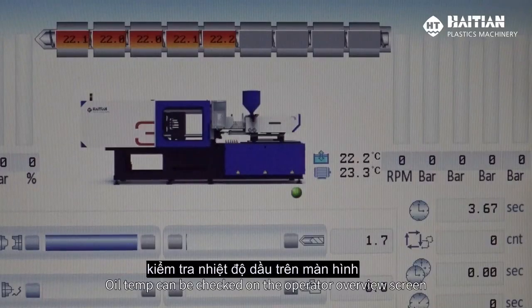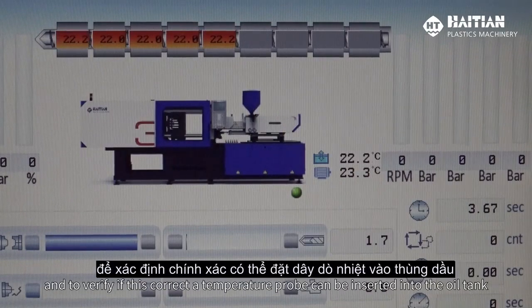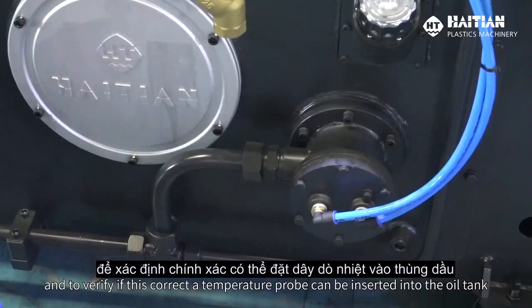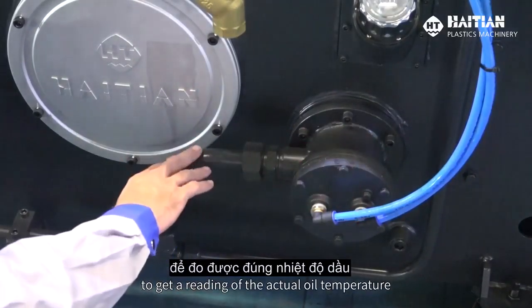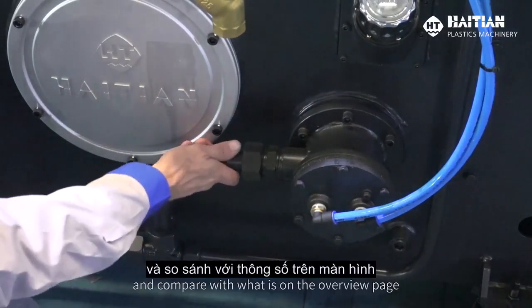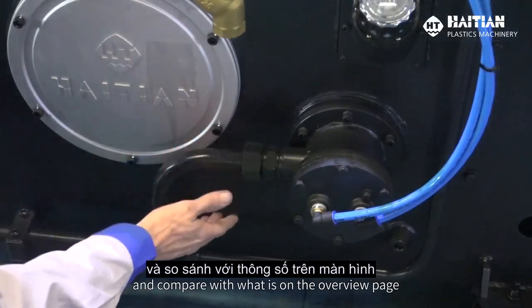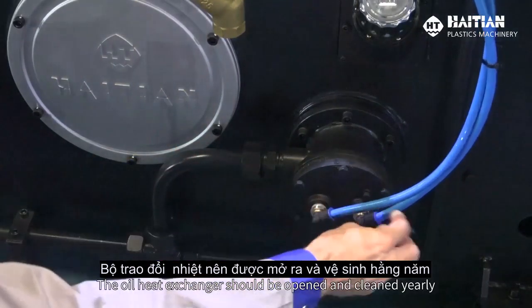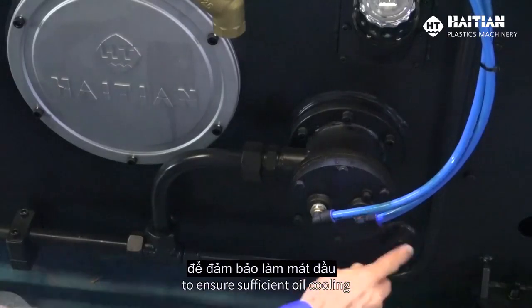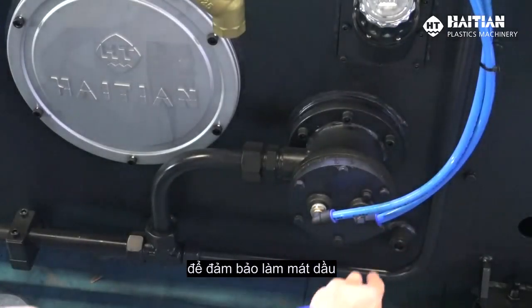Oil temperature can be checked on the operator overview screen, and to verify if this temperature is correct, you can use a probe inserted into the oil tank to get an actual reading of the oil temperature and compare it with what's on the overview page. The oil heat exchanger should be opened and cleaned yearly to ensure sufficient oil cooling.